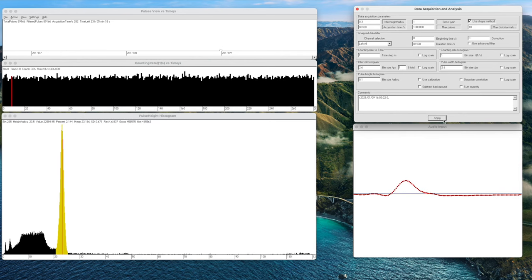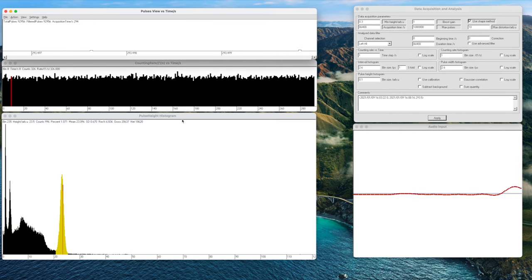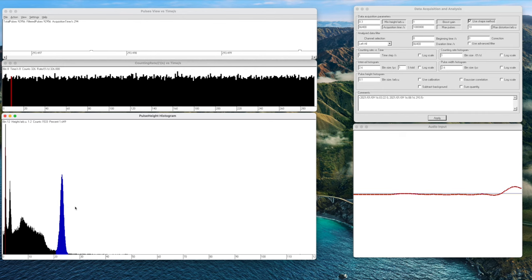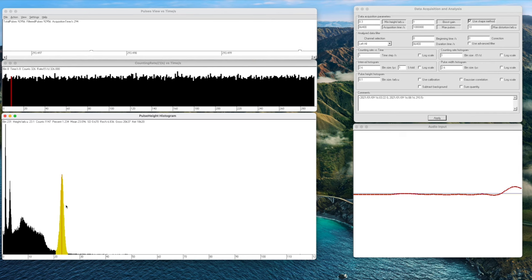That's a nice little feature. Now let's stop the data acquisition for a minute and look at the calibration process. We happen to know the energy of the cesium-137 peak and we also happen to know the energy of the x-ray peak so this gives us an opportunity to get a calibration on this spectrum. Let's see how we do that. The first thing we would need to do in order to get a calibration is to find the peak energy in arbitrary units. In this case 23 point, we can call that 23 even for the cesium-137 peak.